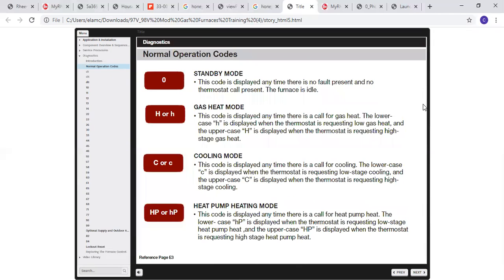So you have your normal operation codes. If you walk up to it, once again, as with the 90s and the 96B, 0 means you're in standby mode, no faults present, and no call from the thermostat. If you have a capital H or a lowercase h, you're in heat mode. Capital is for high stage, lowercase is for low stage. Cooling, same thing: capital C or lowercase c is cooling mode. Capital C is for high, lowercase c is for low stage.